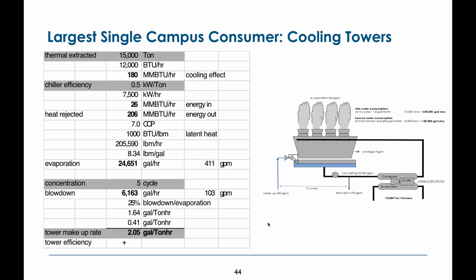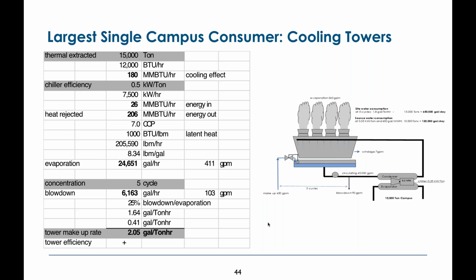The other factor in a cooling tower is the cycles of concentration. That's the amount of water you've got to continuously draw off to keep the concentration of solids in the makeup water from building up to a level where they're going to affect the efficiency of the chiller tubes. This is really the core of the energy-water nexus of a chiller plant. If you aren't spending enough water to keep the purity up, you scale the tubes, and so you're trading water on one side against energy efficiency on the chiller on the other.